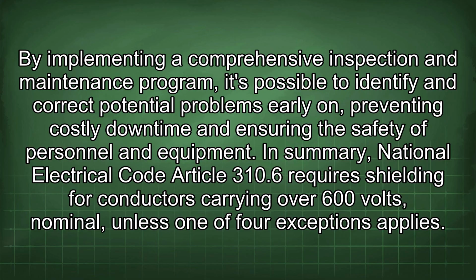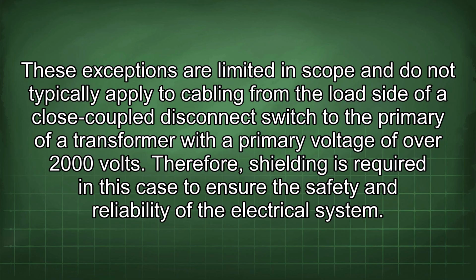In summary, National Electrical Code Article 310.6 requires shielding for conductors carrying over 600 volts, nominal, unless one of four exceptions applies. These exceptions are limited in scope and do not typically apply to cabling from the load side of a close-coupled disconnect switch to the primary of a transformer with a primary voltage of over 2000 volts. Therefore, shielding is required in this case to ensure the safety and reliability of the electrical system.